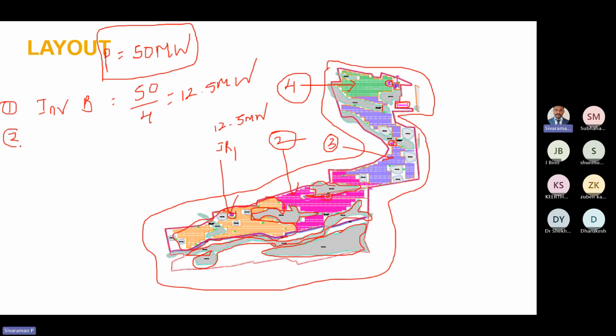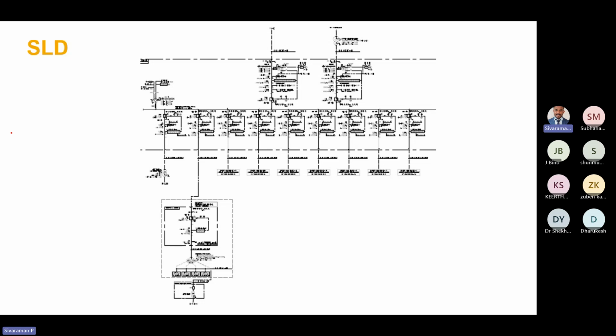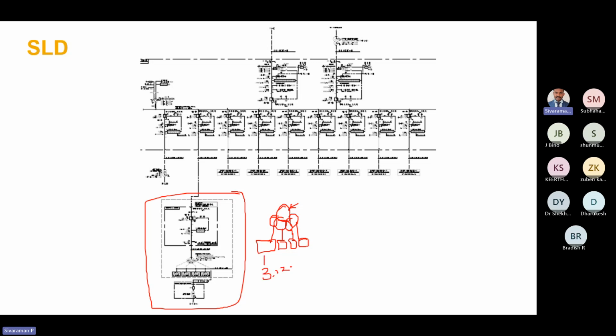Then the second one: what is the rating of the inverter we are going to use? I showed this in the last presentation. This is one inverter room, or inverter block. Here we have a 5 winding inverter duty transformer: one primary winding and 4 secondary windings. On the 4 secondary windings, there will be one inverter each. Each inverter is rated for 3.125 megawatt. So 3.125 multiplied by 4, because we have 4 windings with 4 inverters, so it is rated for 12.5 megawatt.